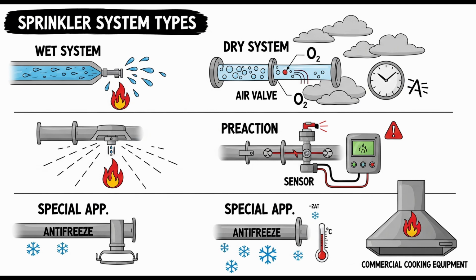Right. The standard also notes that dry pipe systems with different water delivery times can be acceptable if they are tested and listed for that specific performance. Allows for innovation. Let's talk about splitting up dry pipe systems. The source says you generally can't subdivide them using check valves unless they're in a heated enclosure. Why not? Right. A check valve outside a heated space could trap moisture or small amounts of water between it and the main dry pipe valve. That trapped water could freeze and block the system or cause damage. Makes sense. So if you do use check valves for subdivision, they have to be in a heated box or room. Correct. They must be located within a heated enclosure.